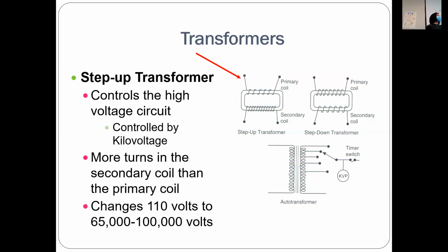But what happens first is the step down for the mA production of the electron cloud. Push the button, step up to accelerate the electrons. So it steps down to create the electron cloud, then steps up to increase the voltage to accelerate them over to the anode.